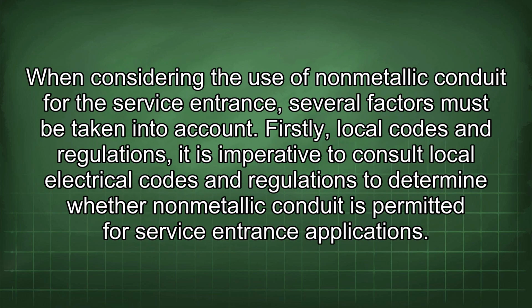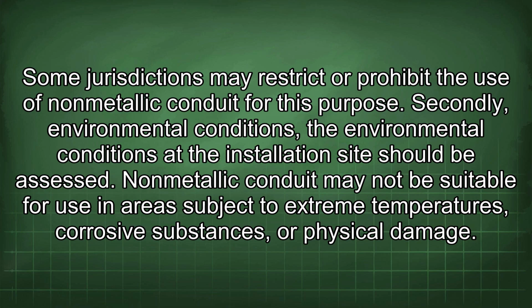When considering the use of non-metallic conduit for the service entrance, several factors must be taken into account. Firstly, local codes and regulations. It is imperative to consult local electrical codes and regulations to determine whether non-metallic conduit is permitted for service entrance applications. Some jurisdictions may restrict or prohibit the use of non-metallic conduit for this purpose. Secondly, environmental conditions. The environmental conditions at the installation site should be assessed. Non-metallic conduit may not be suitable for use in areas subject to extreme temperatures, corrosive substances, or physical damage.